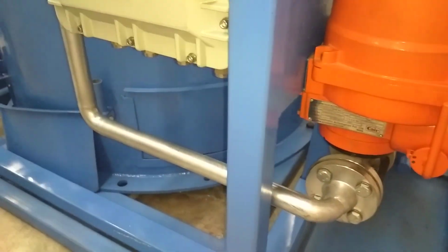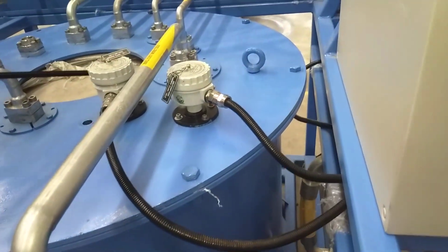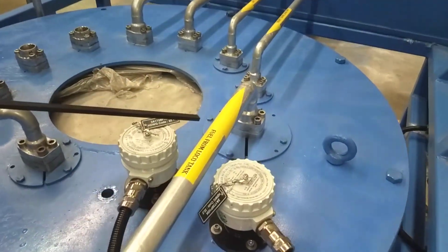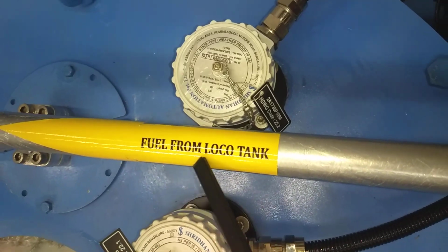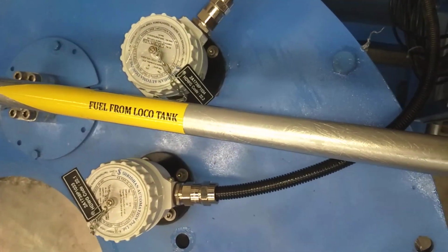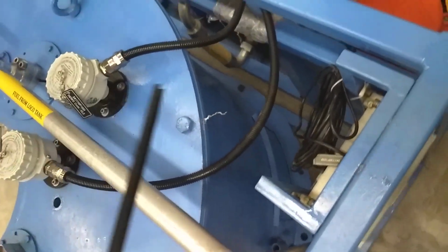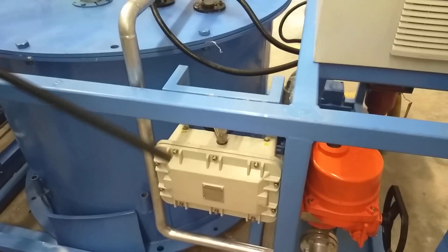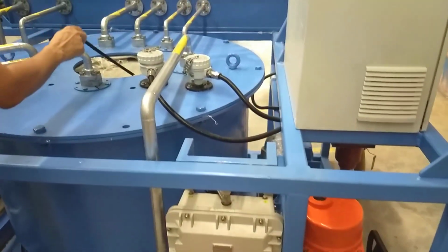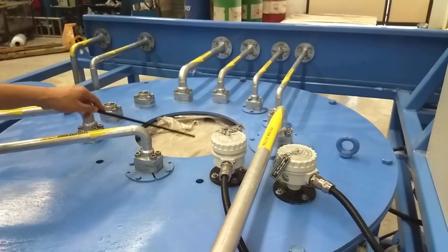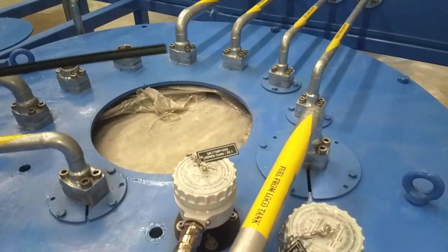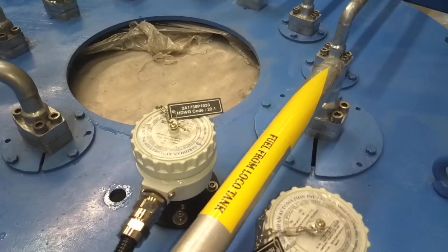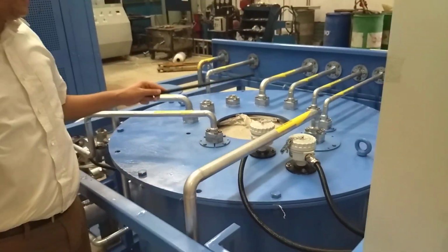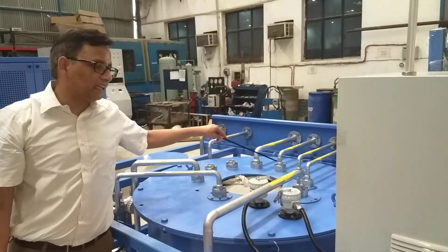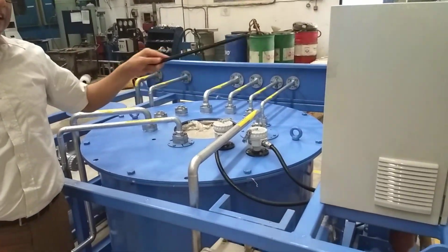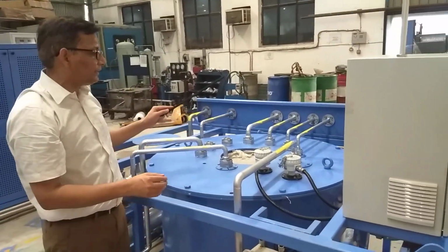So this pumped fuel is coming through this, and as you see, this line is coming, and this line is going into the tank, and my colleague will show this label. It says fuel from loco tank. So the fuel from loco tank is pumped through our own electric motor and pump, through those valves and the filter, and it is getting filled into the tank. Now this tank has a level switch, which is again explosion proof, because of diesel, the electronics is explosion proof. This level switch tells us when the fuel in the tank is completely filled. Then automatically the pump will stop and the valves will stop.